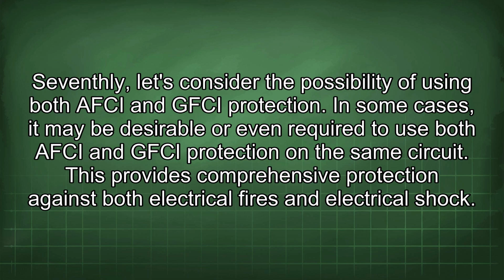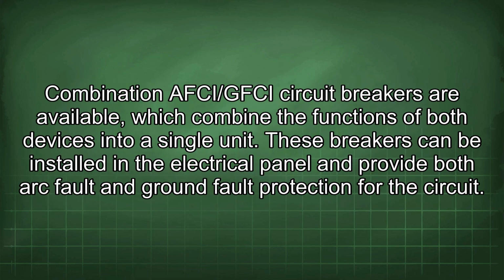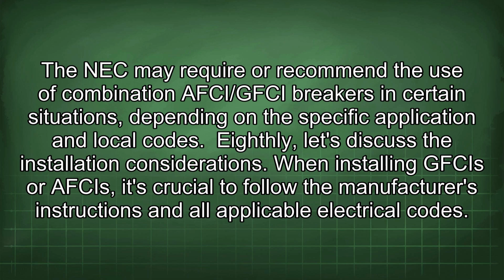Seventhly, let's consider the possibility of using both AFCI and GFCI protection. In some cases, it may be desirable or even required to use both AFCI and GFCI protection on the same circuit. This provides comprehensive protection against both electrical fires and electrical shock. Combination AFCI/GFCI circuit breakers are available, which combine the functions of both devices into a single unit. These breakers can be installed in the electrical panel and provide both arc fault and ground fault protection for the circuit. The NEC may require or recommend the use of combination AFCI/GFCI breakers in certain situations, depending on the specific application and local codes.